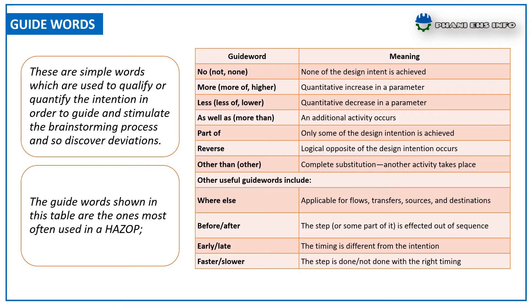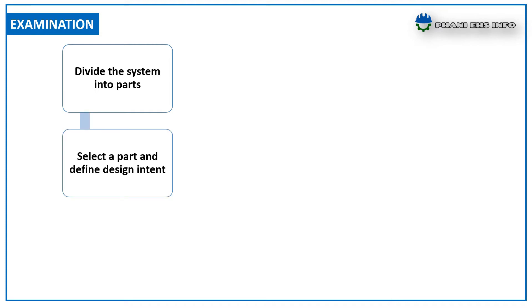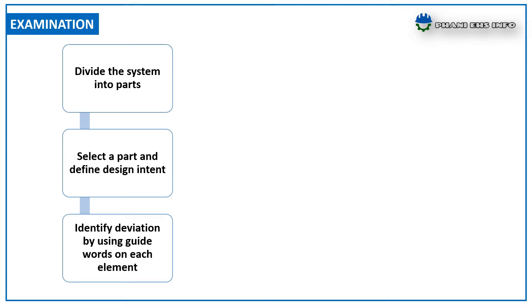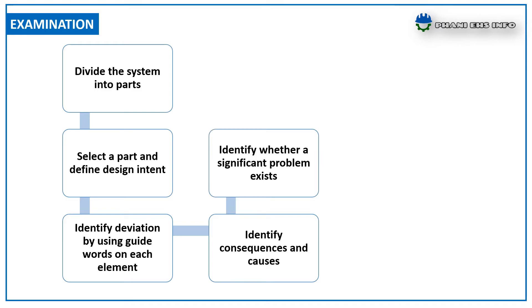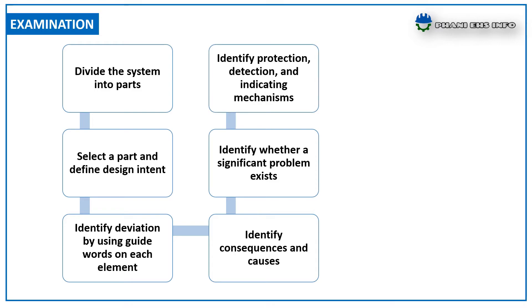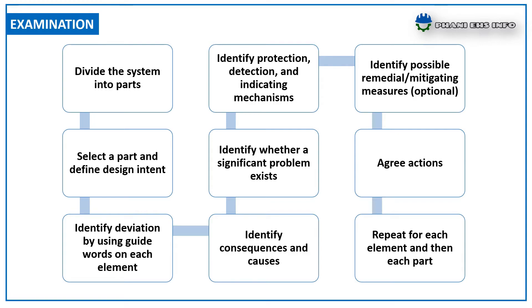WHERE ELSE applies to flows, transfers, sources, and destinations. BEFORE or AFTER means the step is affected out of sequence. EARLY or LATE means the timing is different from the intention. The examination phase includes the following steps: divide the system into parts, select a part and define design intent, identify deviations using guide words on each element, identify consequences and causes, and identify whether significant problems exist.